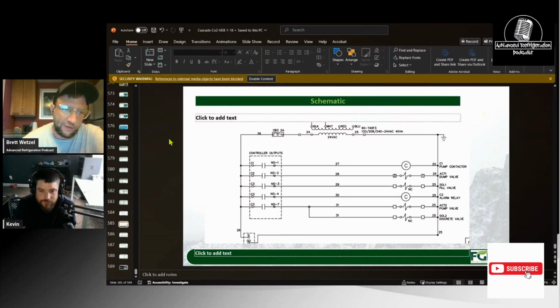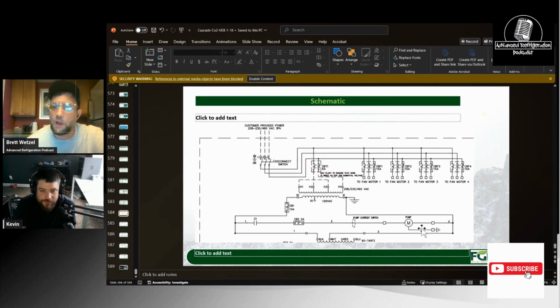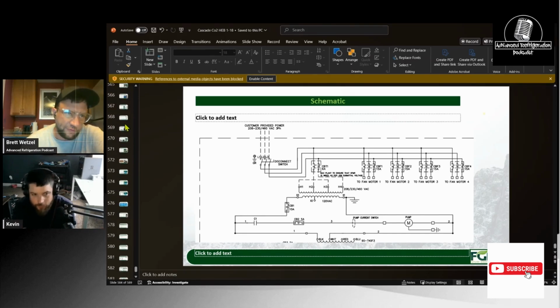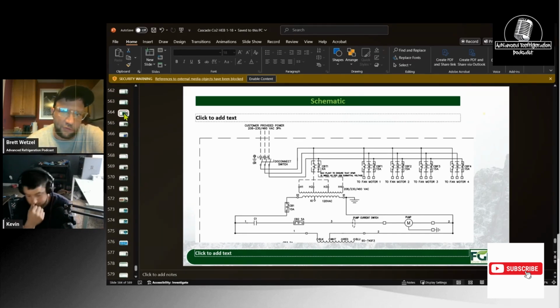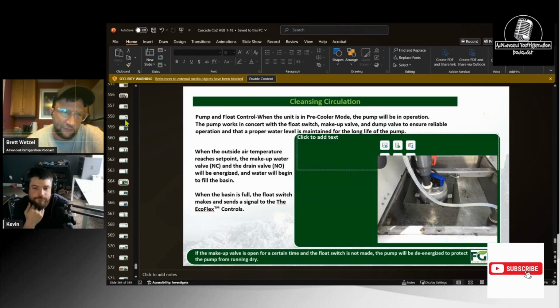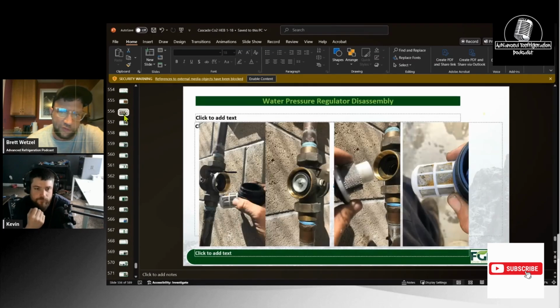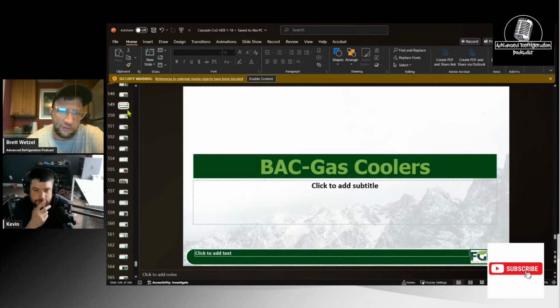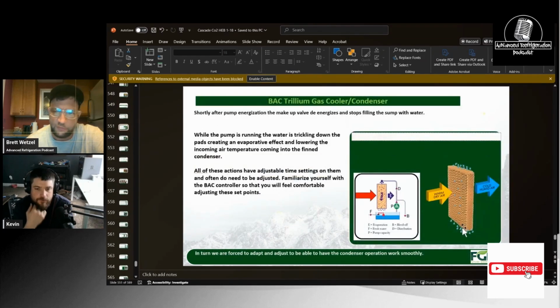I think the only thing that's actually 120, if I go one more up, yeah, the only thing that's the pump. Yep. Yeah, there's that. But like I said, essentially what we're doing is, the water is all being controlled by BAC. The only thing we are doing, we're giving it set points in that, but the only thing we're essentially doing is basically giving it a signal to basically run the pump, to drop the water across the pad, take that warm air to make cold, humid air.